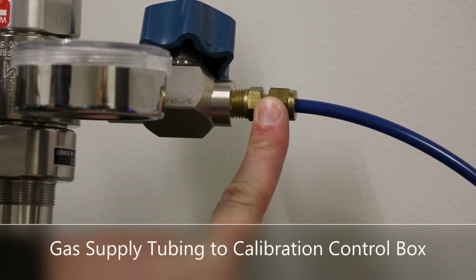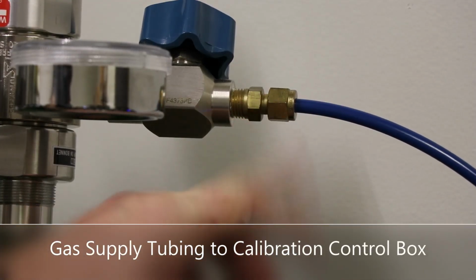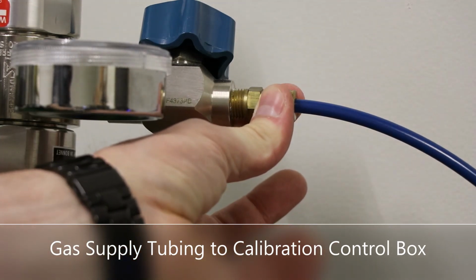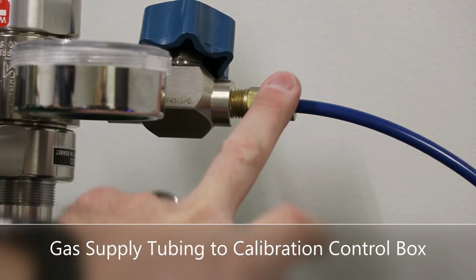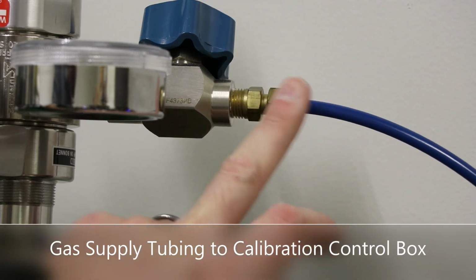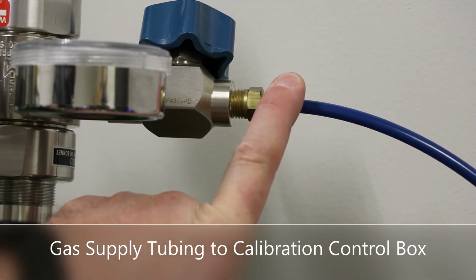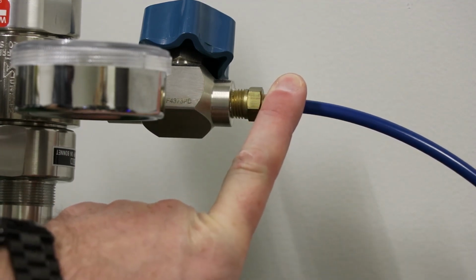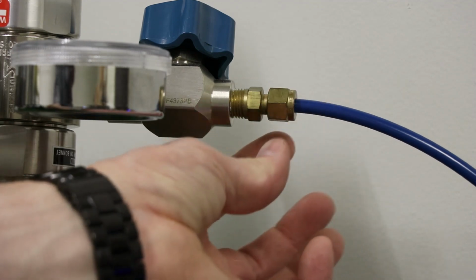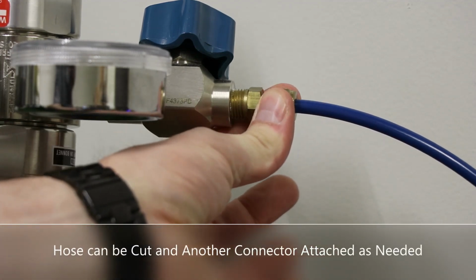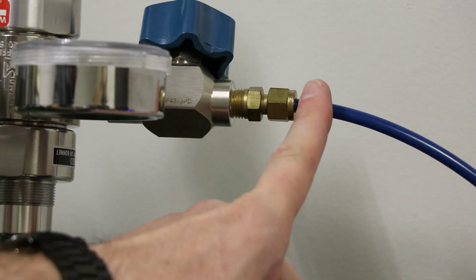The nitrogen and oxygen lines that connect to the back of the cal cell are connected here on a dual stage regulator. So there's two fittings that are supplied, one on each end of the tubing. These are 1/4 inch, they're called Swagelok gas fittings. They're air and water tight. If this is not the connection that you have or need, you can cut this line and put on the appropriate connector.